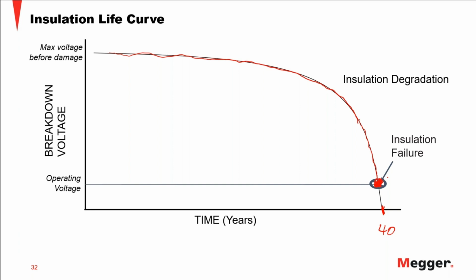So you want to test throughout the life, and you want to test not only at the operating voltage. You want to test in a range that is going to give you that analogy of finding a pressure leakage, but it's not going to damage the insulation, because if we apply a voltage that is close to this maximum voltage capability, then we're going to break down the insulation. So that is what the insulation test does.